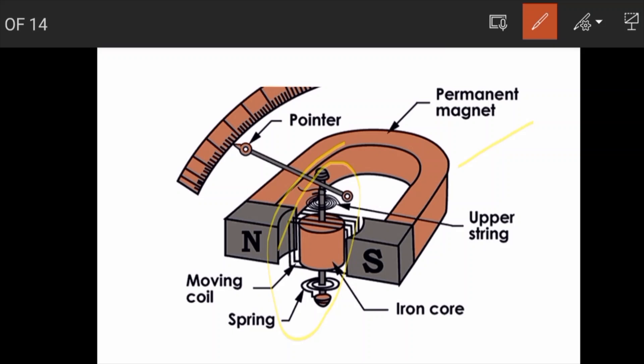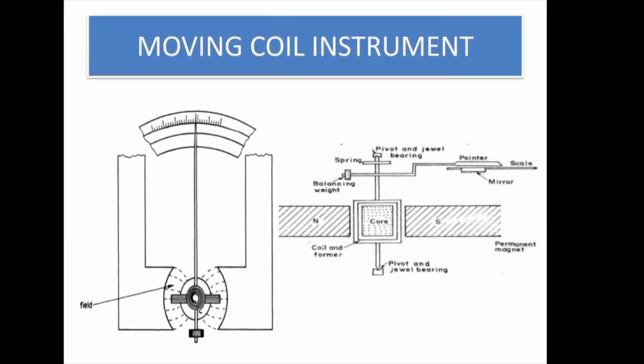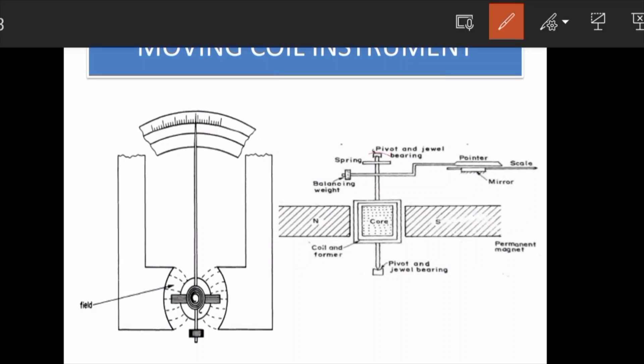The pointer moves across the scale due to deflection torque. There must be an opposing force — the controlling torque — to balance the deflection. This controlling torque is provided by the phosphor bronze spring, which also carries the incoming and outgoing leads of the current.